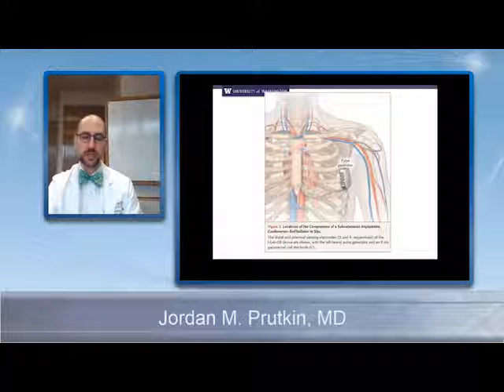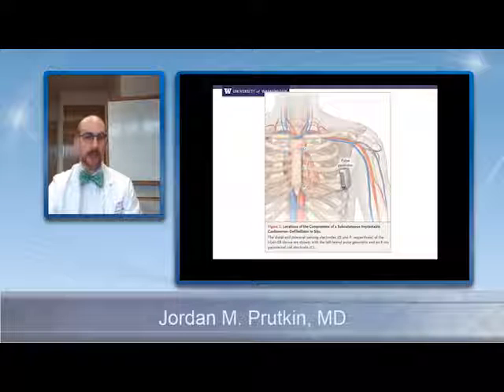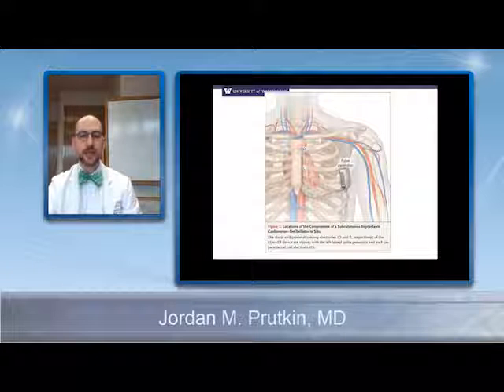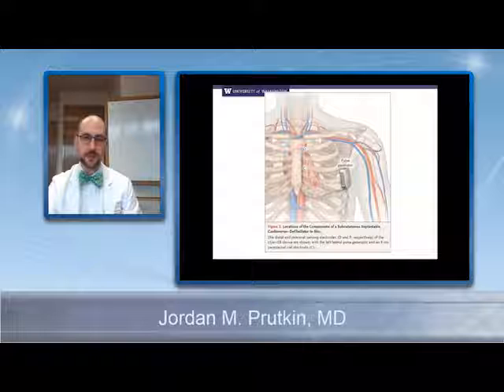And when it shocks, it's shocking between the generator and this coil that's right here, the C, and it shocks across this vector. When it does its sensing, it's either doing it from the tip to the generator, from an electrode down here to the generator, or from the tip to this electrode. And the device is programmed to choose which of those vectors it uses. In some ways, this is more like an implantable AED as opposed to a traditional defibrillator. This device is really designed to shock the heart, and that's it. It doesn't do any pacemaking. It only does about 30 seconds of pacing after a shock if it's needed, but it's not like a traditional defibrillator that has a pacemaker built into it.